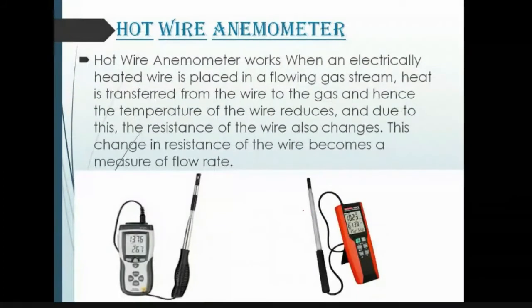Now moving on to the next topic, hot wire anemometers. A hot wire anemometer works when an electrically heated wire is placed in a flowing gas stream. Heat is transferred from the wire to the gas, and hence the temperature of the wire reduces, and due to this the resistance of the wire also changes. This change in resistance of the wire becomes a measure of flow rate. Here below we have shown you two digital hot wire anemometers.